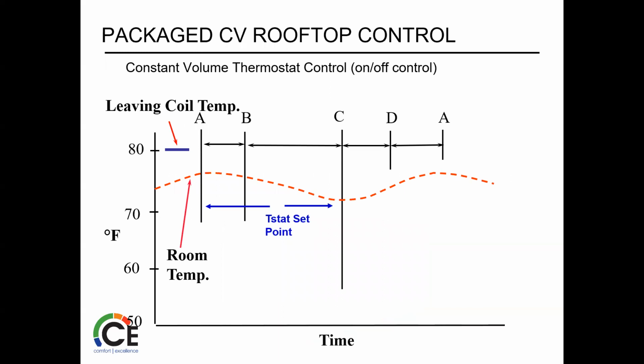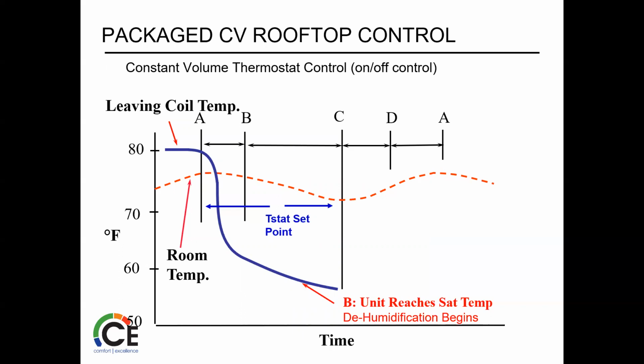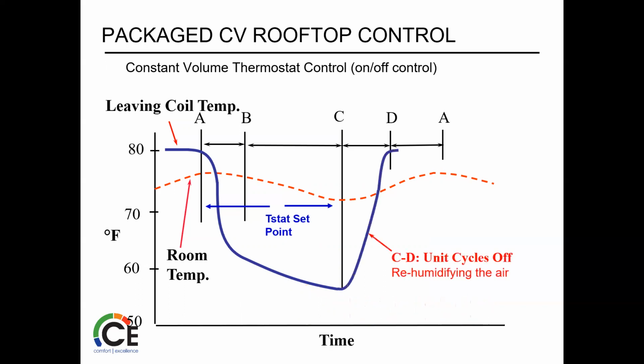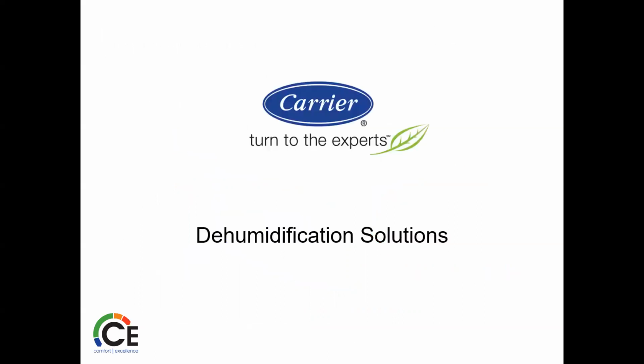So just a basic package, rooftop, constant volume thermostat, it's just on and off, right? So the unit cycles on, we haven't reached saturation yet. So at this point, no dehumidifying yet. We're blowing some cold air, but that's all we're doing. And once we get to that saturation temperature in the refrigerant, we're starting to dehumidify a little bit. And of course, once we hit the set point, everything cycles off, and any moisture in that coil, now we're blowing air through it and we're throwing humidity right back into the space. Maybe not as much, because we pulled some out thanks to our condensate line. We see it dripping, but we're still doing that again. And as that stays off, we get right back to the same cycle again. So we're going to redo it again.